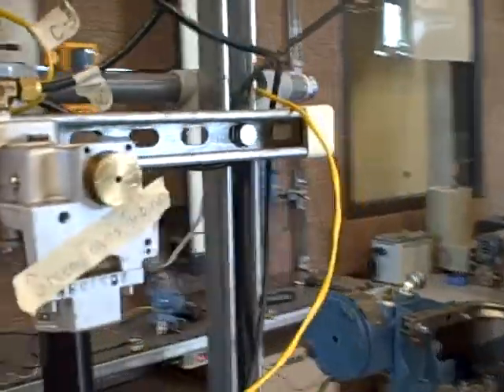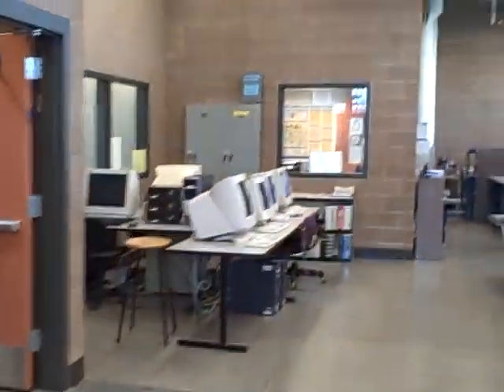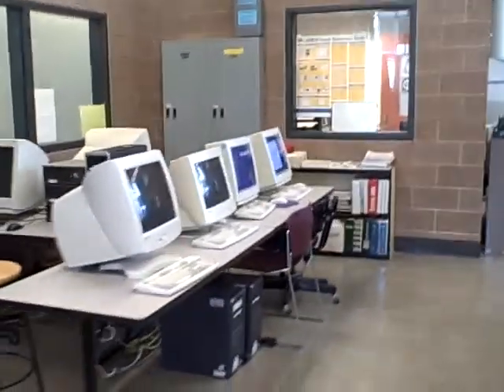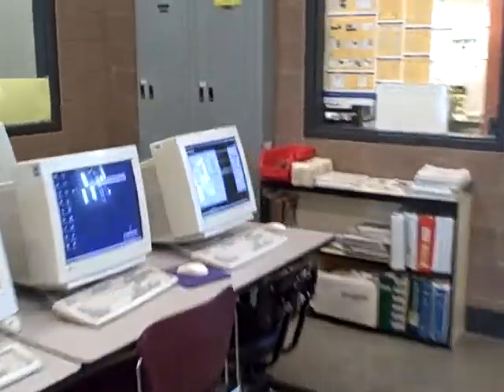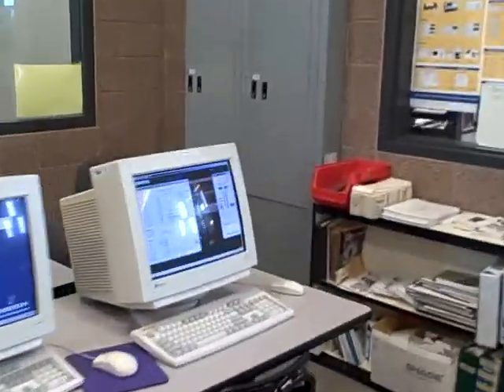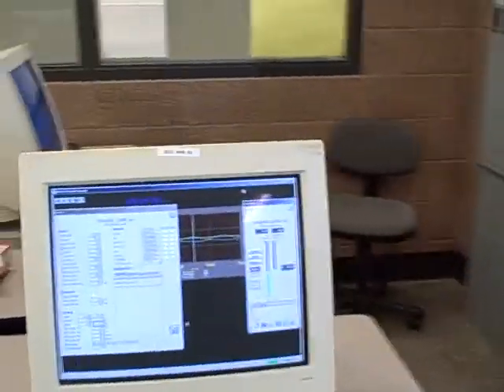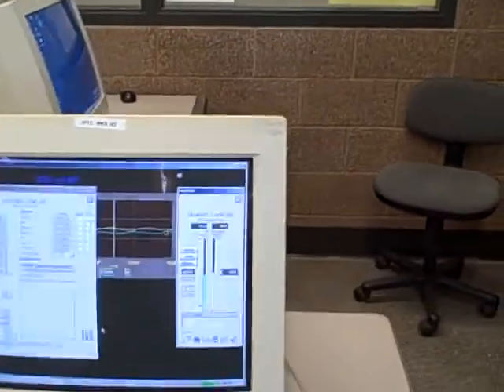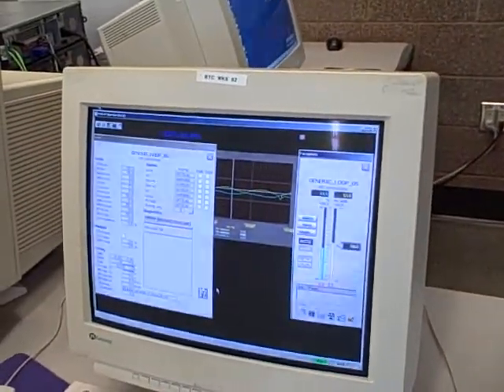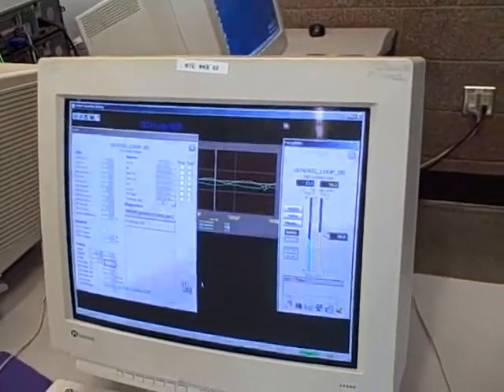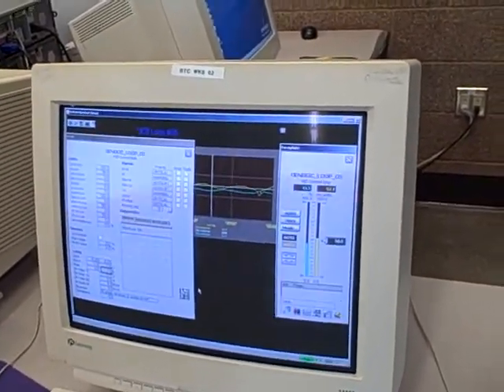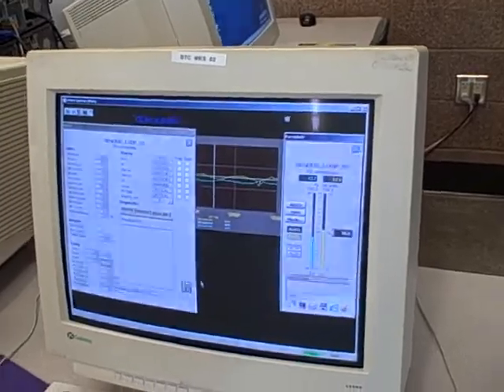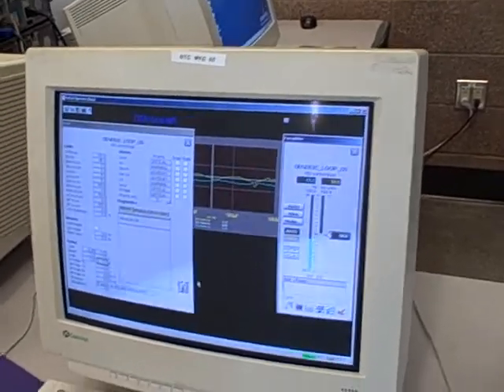This is a surprisingly tricky process to control because the turbine itself has friction that comes and goes. We have a bearing that's going bad, probably in the tacho generator, and so that presents an occasional, almost random, load to our system. It causes the speed to jump up and down unpredictably, and the valve, of course, has to compensate for that.